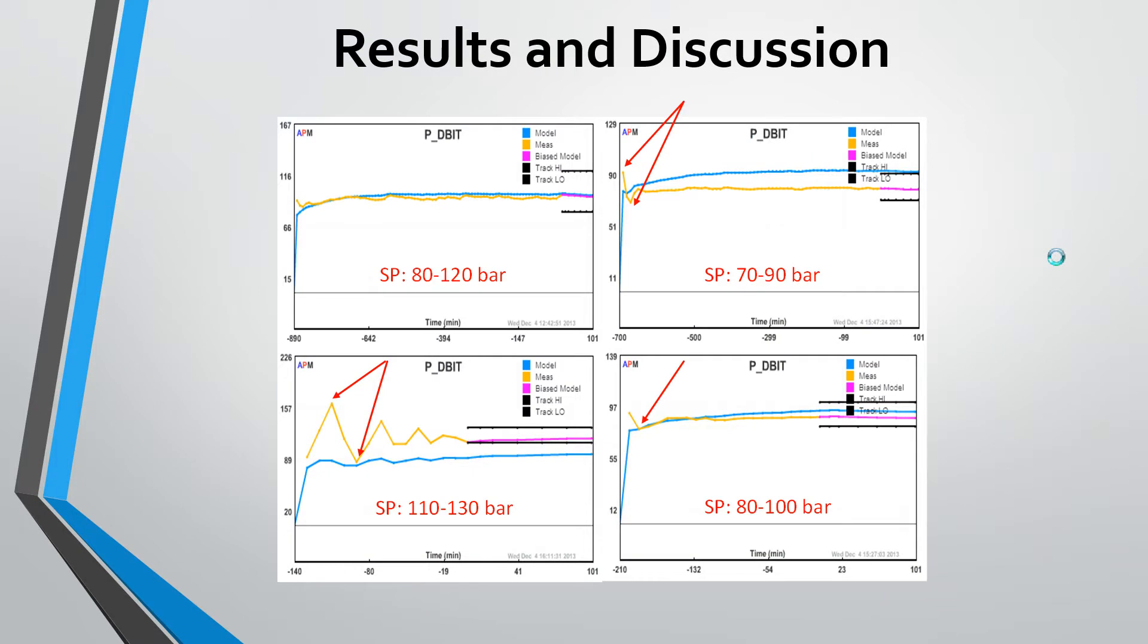Here are the results that we got from running our controller, which worked very well. The black lines here in each figure are the dead band, and the blue line shows what the model predicts is going to happen. The yellow line is what's actually happening, and the pink line is the bias between the two. This top left figure here is our base case with the set point of 80 to 120 bar. You can see that the controller worked very well. It follows the model and then it stays within our dead band.